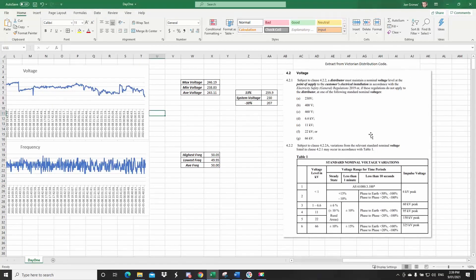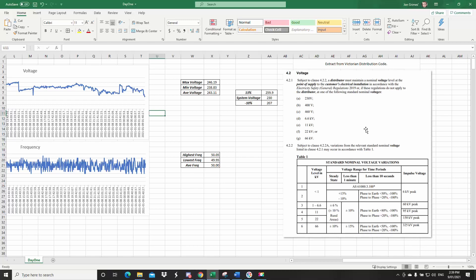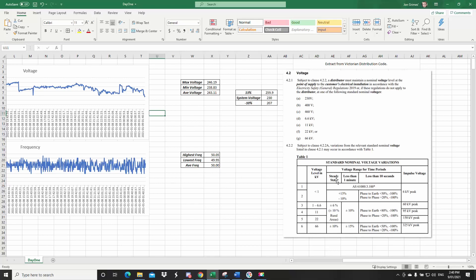So now this is an extract from the Victorian distribution network code. So this is straight out of it and it tells us the system voltages and then for those voltages what the tolerance limits are. So we can see that for the steady state voltage, this is really the only one that I can check with the data that I'm collecting. So less than one minute, I haven't done less than one minute, so I can't collect that, but it's going to be the same. Less than 10 seconds, I have nowhere near enough data to have a look at that.